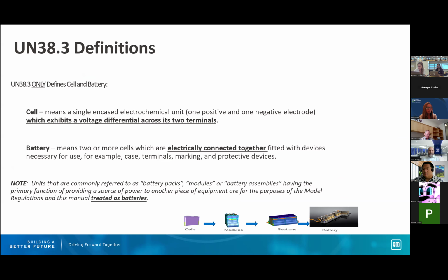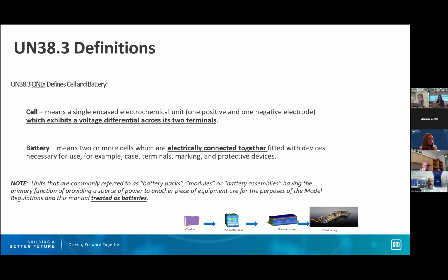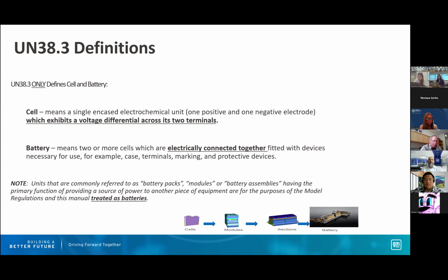Battery packs and modules — I have a visual below showing the transition from a cell into a module, or a battery into a larger module, and then into a pack where they're all contained. Those are the different options, and all of them fall under UN 38.3. It's important to note that if I change any of those — the cell, the hardware, the terminals, the bus bars, the wiring, or any protective fuses — any of those changes would be considered a new design type, pushing me back through to retesting.